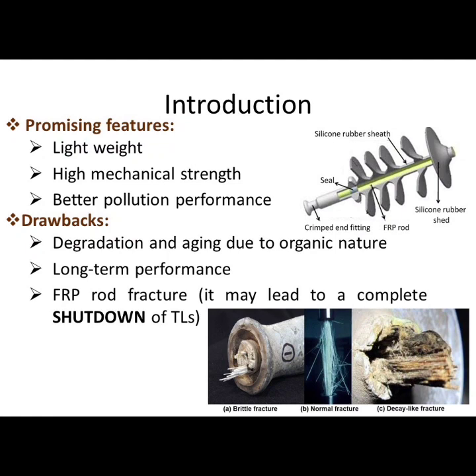Also, it provides a high mechanical strength and improved pollution performance due to the hydrophobic nature of the silicone rubber. The main components of these polymeric insulators are the FRP rod, silicone rubber housing, and metallic end fittings. The FRP rod provides the internal insulation and the required mechanical strength. The silicone rubber housing provides the required creepage distance to limit the leakage current and also protects the FRP rod against the various electrical and environmental stresses.